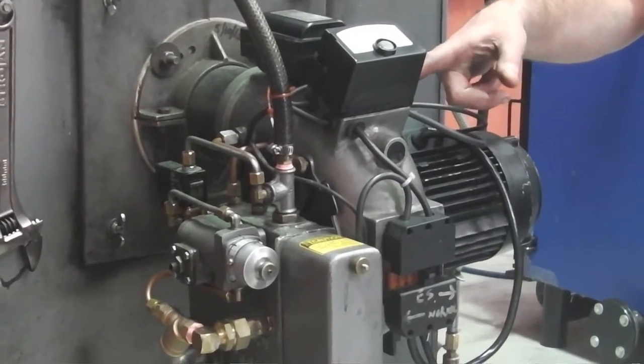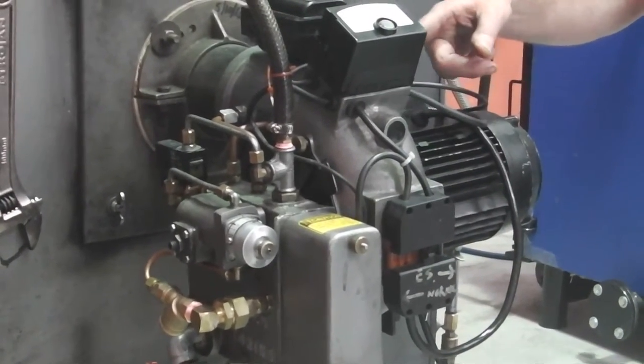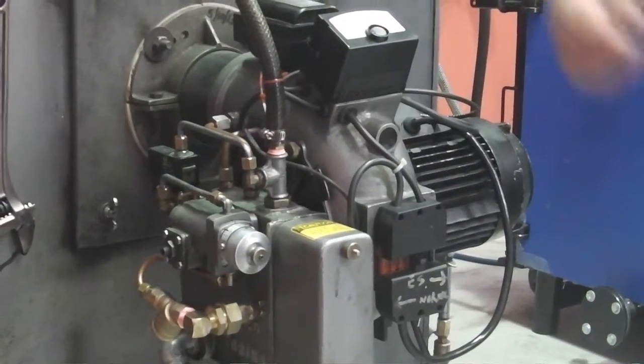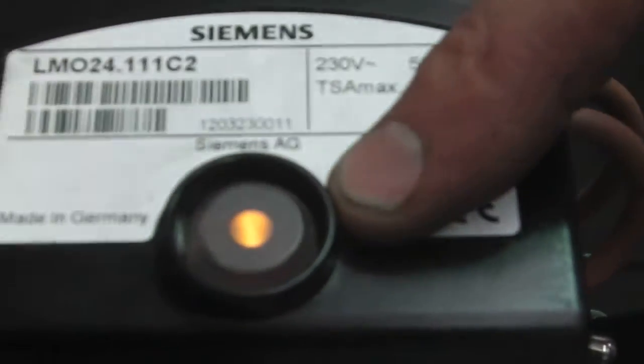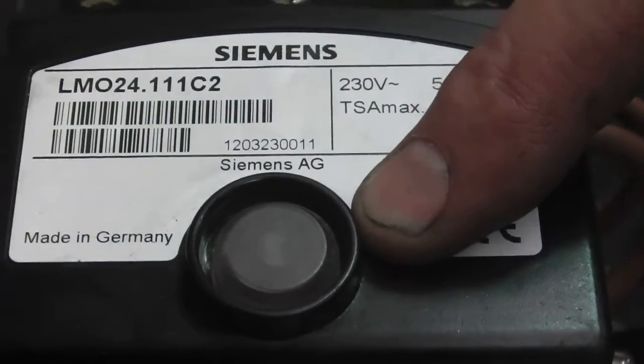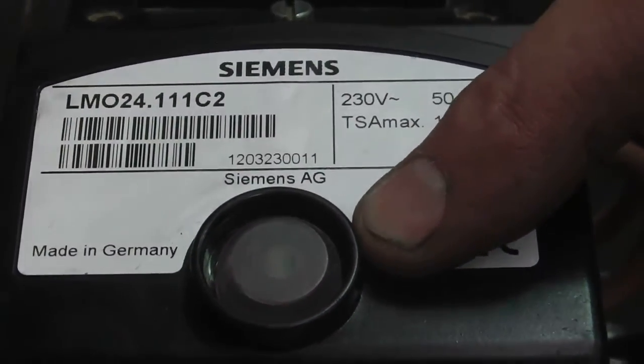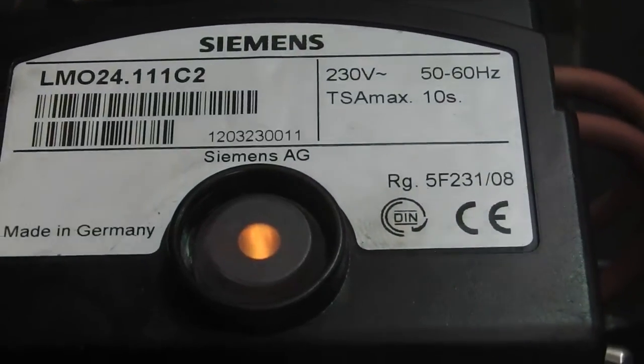I'll put it on now, and we'll get Pete to walk in and take a shot at the flame. You can hear the motor spinning up. There's always a delay of about 12 seconds. If it's blinking orange, that means it's in a purging cycle. This will last for about ten seconds. Let's have a look at the ignition.